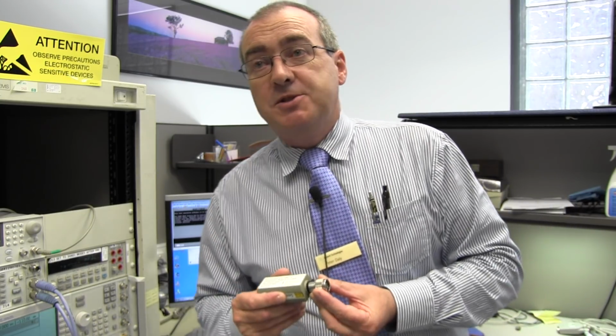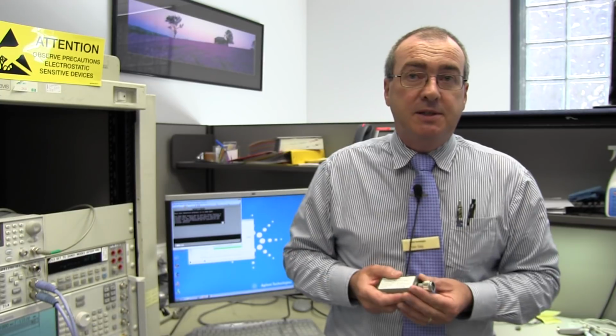One of our customers turned around to us at one stage, because we visited them every year and did all their equipment, including their cal kits. They were spending between 10 and 15 grand a year on repairs of their cal kits, just repairing connectors that we'd picked up as part of the calibration. They turned around to us and said, these products are unreliable, and it's a bit of a red flag to a bull, and we said, it's not the product, and we used the example of ours.